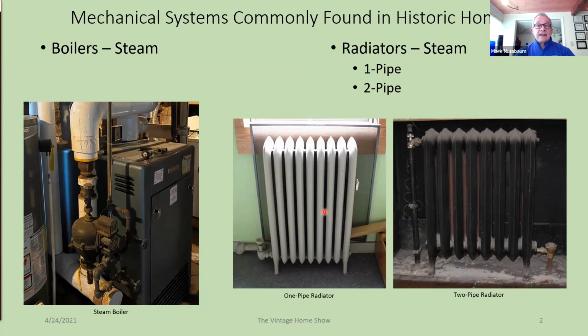The water that comes out of that steam then has to go back out that same pipe. So one of the things you want to be sure not to do on these is throttle this valve, or else you can cause water to back up, or you cause steam knocking and things like that. The other type of steam system you're likely to find in a historic house is a two-pipe radiator. In that case you have steam entering through a valve, either at the top or bottom, and on the other side you have a pipe leaving with a small thermostatic trap, and that trap does the same thing as that air vent. It's looking for condensate or steam, so when it senses steam, it shuts off so that steam stays in the radiator and doesn't go back down to the boiler until it's ready.